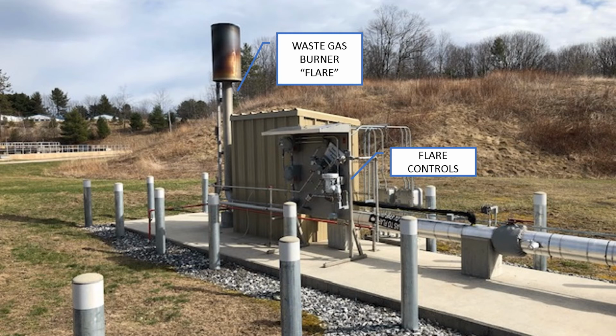So at about 8½ inches of water column within the gas piping system, the gas regulator will open up and send itself over here to the flare. We do run a pilot off natural gas that's always on standby and lit. So with a lit pilot, pipe full of gas, you can quickly get a 10-foot flame.